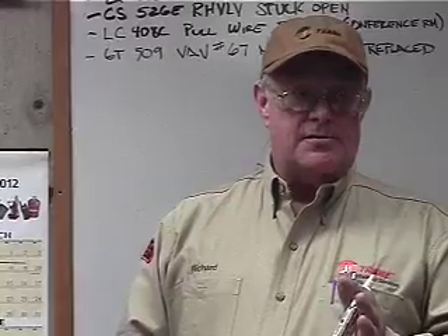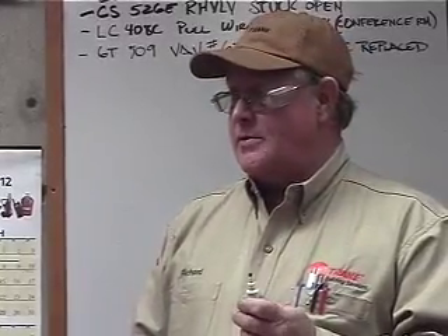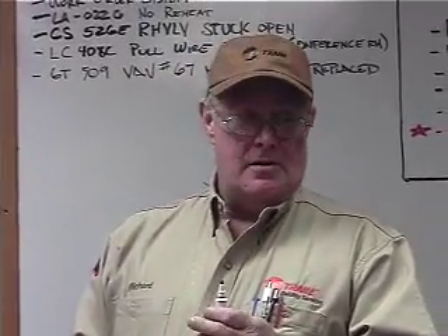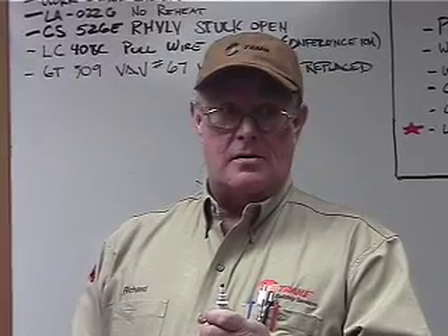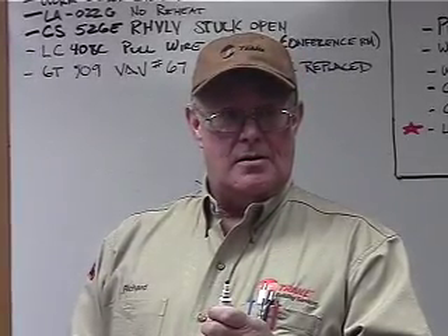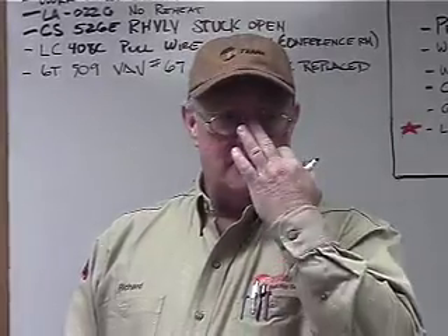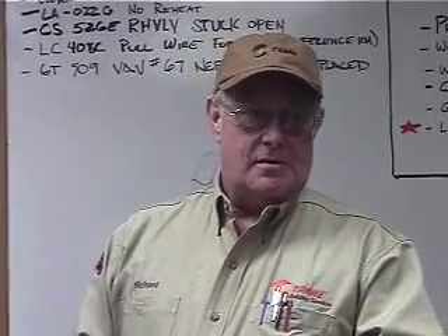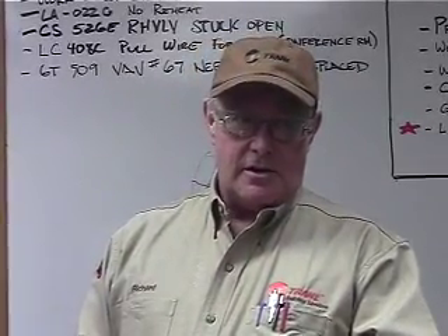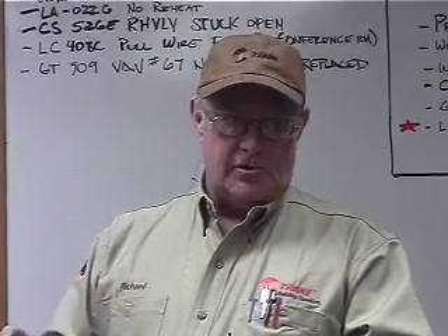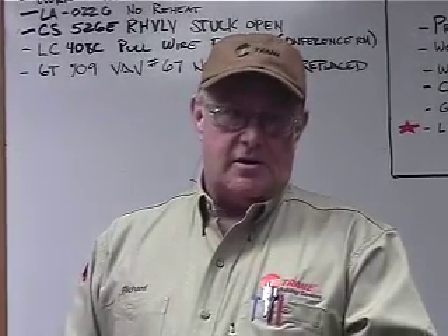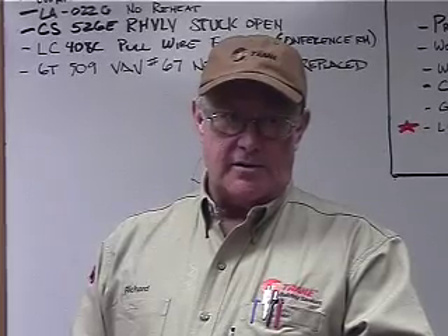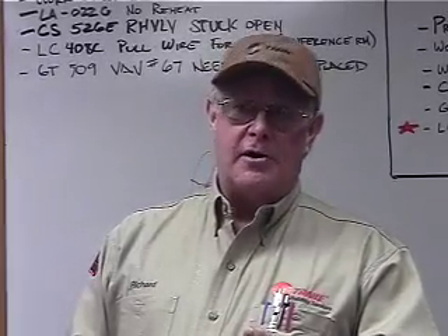Anybody had any problems with the chillers that you want to talk about? We've heard that screeching before on our Yorks. Up on the cooling tower? Well, no, at the York. Oh, it was due to the cooling tower? Yeah, because the condensing water was too hot? Hot, yeah. That'll happen on these also.